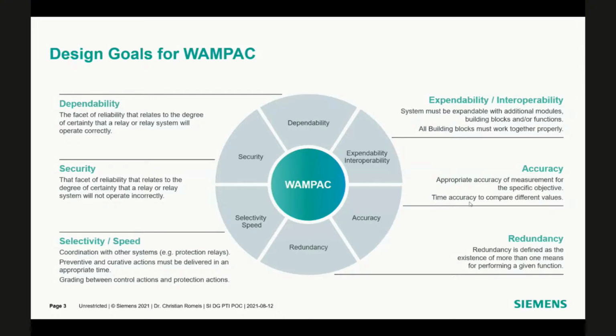If you introduce a protection scheme, you have to be very fast in system splitting. Also in control schemes, if you close the loop, you have to be very careful with latencies so the action is delivered at the right time. On the right side, expandability and interoperability are very important for the WAMPAC system, so that you can expand it at any time with different vendors, different building blocks, and different applications you want to introduce.